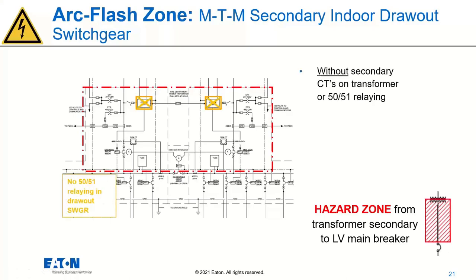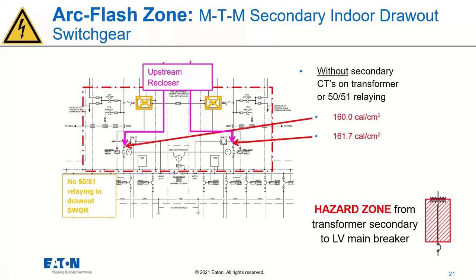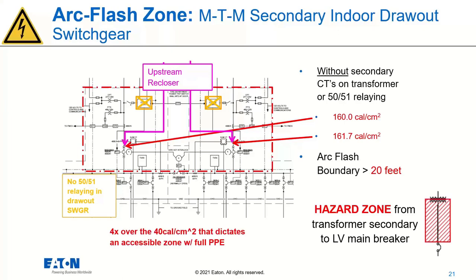So without that 50-51 relay, with just the upstream recloser, we're looking at about 160 calories per centimeter squared in that arc flash hazard zone. That's a very high arc flash energy. If you remember, I just mentioned the 40 calorie limit. So that's four times over what would be really accessible with any PPE per OSHA. And really that's even 60 calories above any PPE that even exists. This is extremely high energy. This is a scenario where you must de-energize in order to work on this equipment.